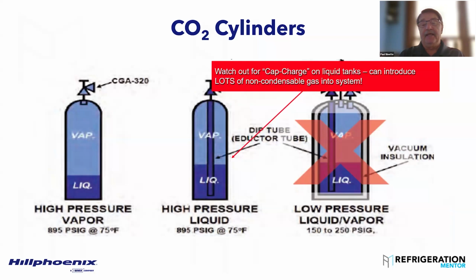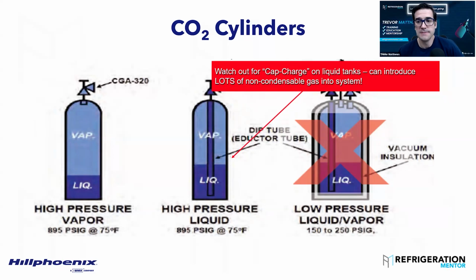But you need to filter it, and then run it, and then check for non-condensables and vent any non-condensables. And if you're on a system where the condenser and the vessel, the flash tank, are equal, or the condenser is below the vessel, you're going to have non-condensables in your flash tank too. So be aware of that. That's another place you'll want to vent them off. Yeah, so this is the highest point.